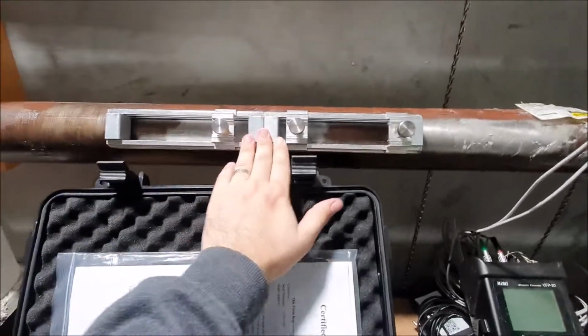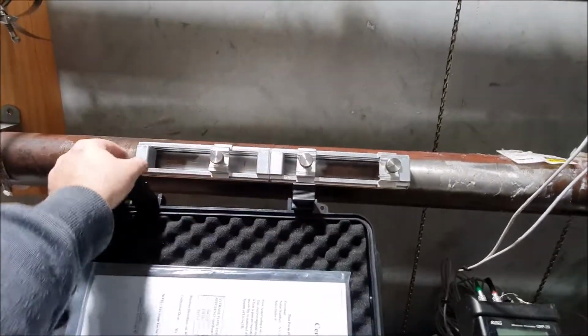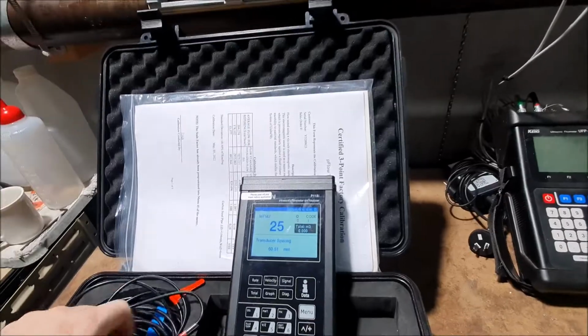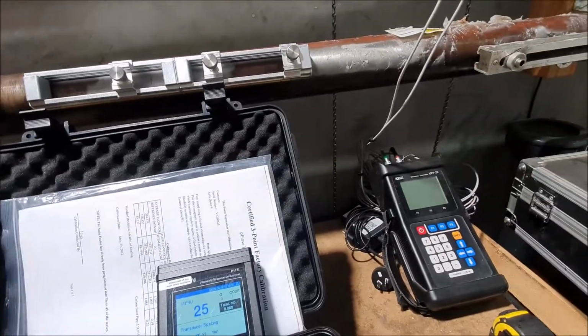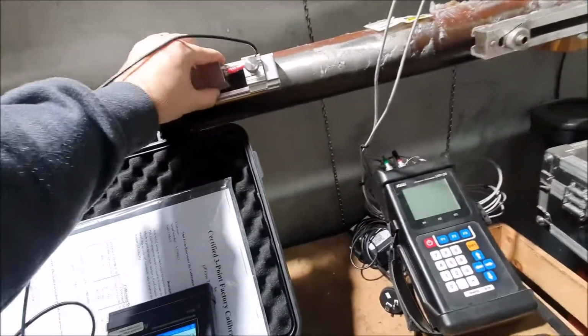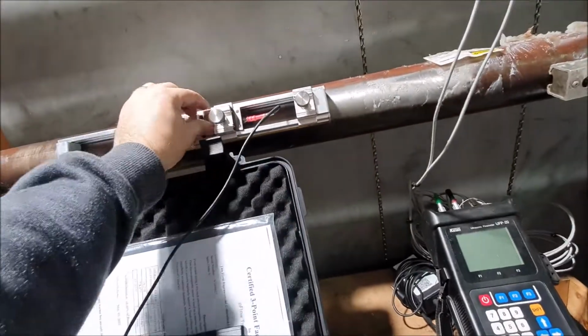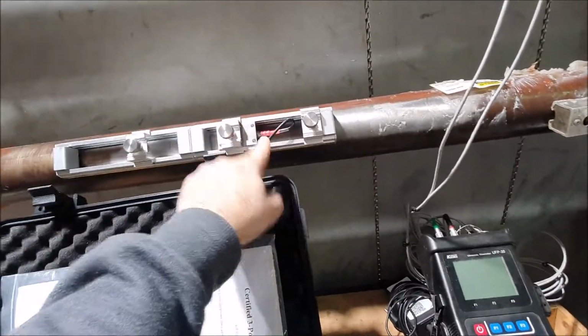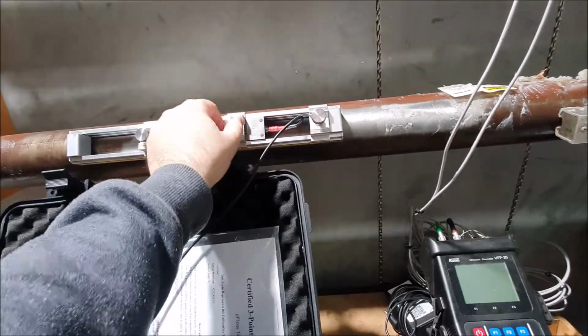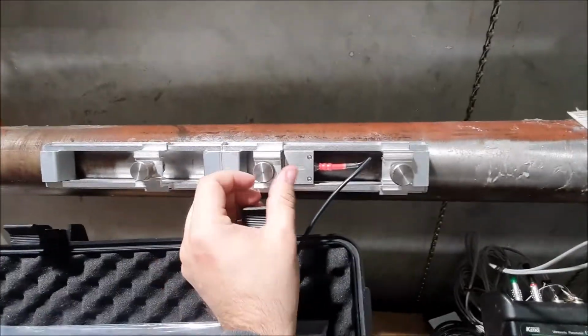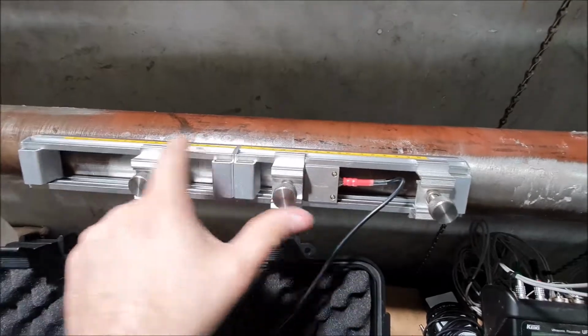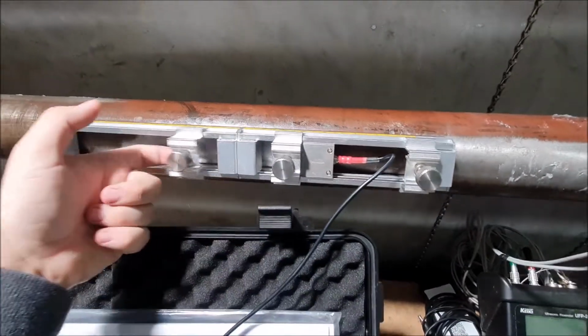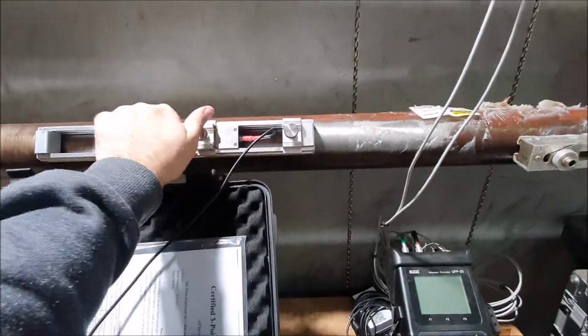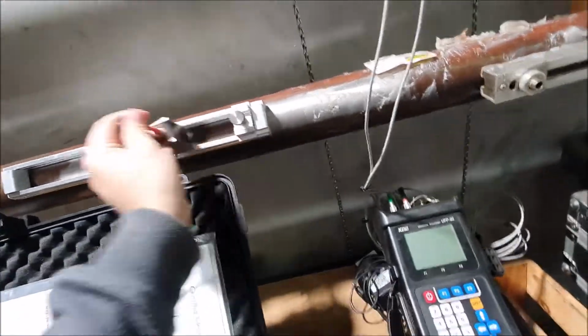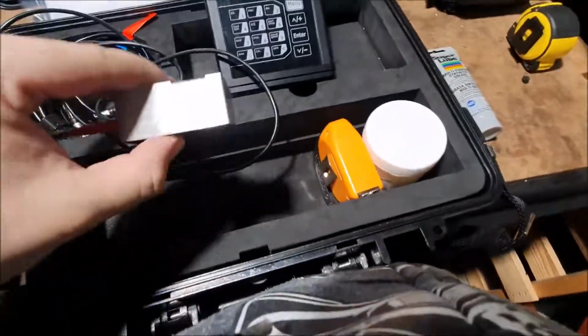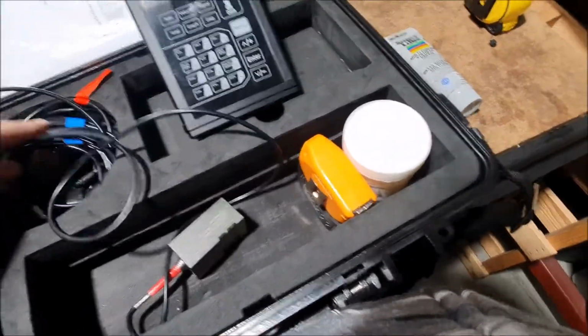It's just mounting the transducers. In this case, this is a magnetic mount, and then the transducers aren't magnetic, so you can slide these into the frame. Essentially, what we're going to do is slide them into the frame. We need to put some couplant on the back of the transducer, and then we're just going to tighten this frame down in place, and then just checking the distance between them. We'll have another transducer in here, obviously, and then tighten it all down. But what we need to do first is check which one is upstream and what is downstream.